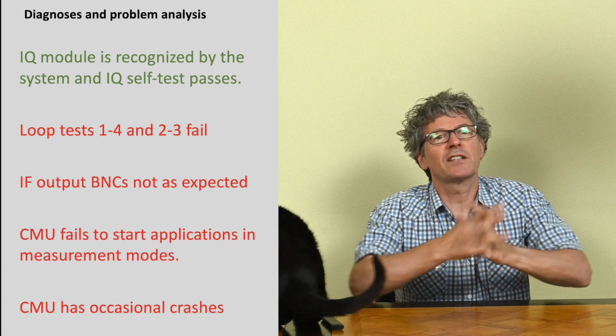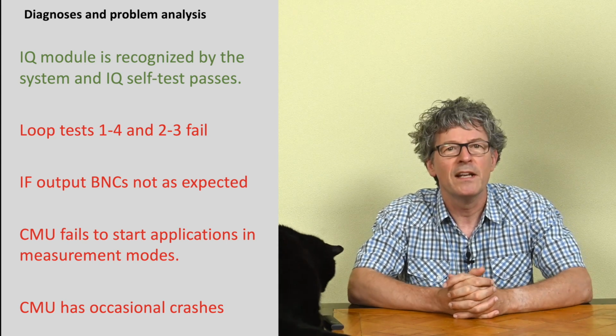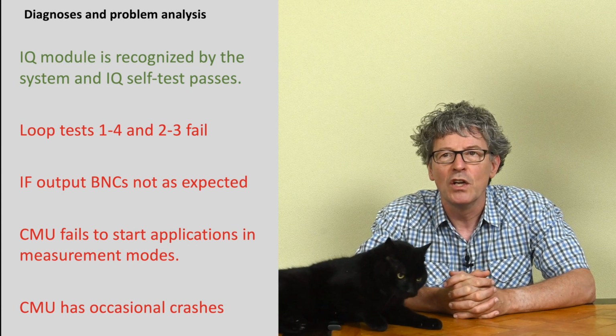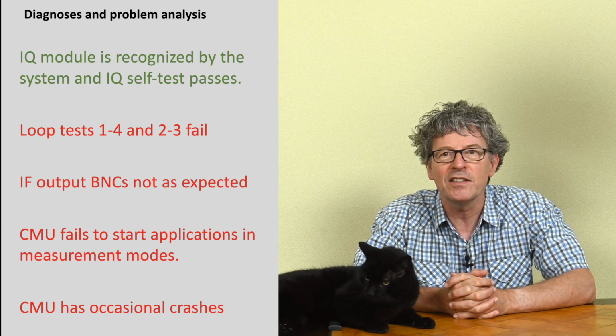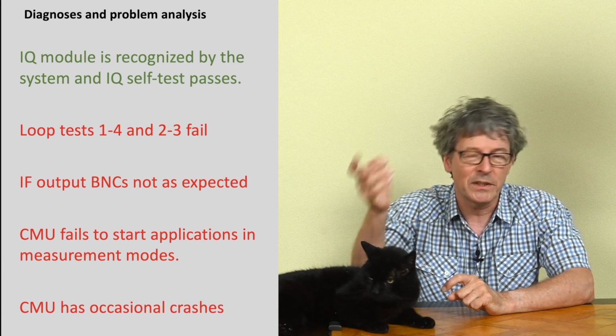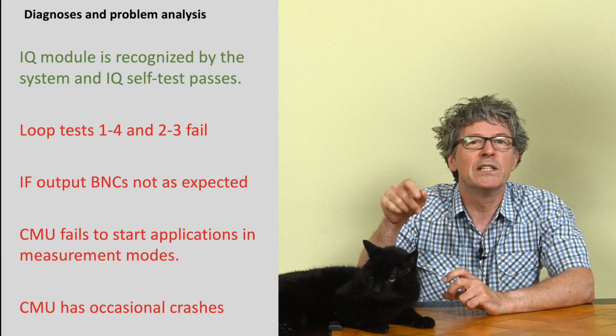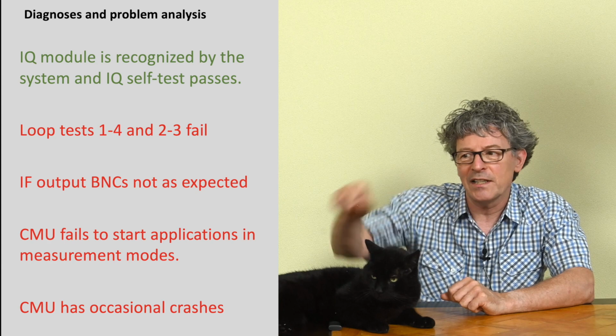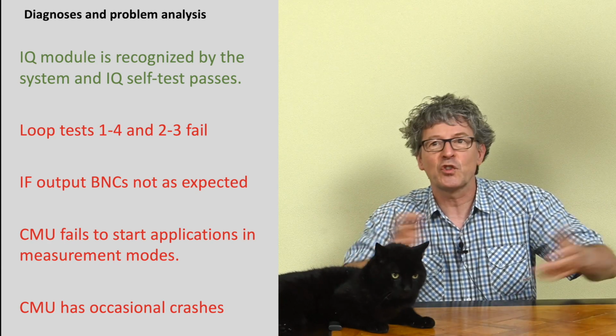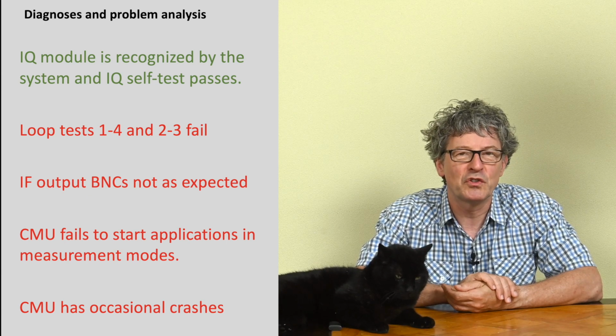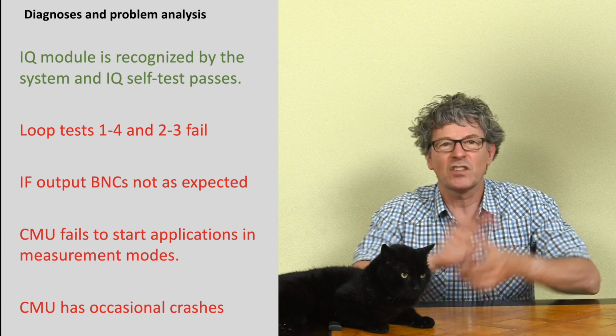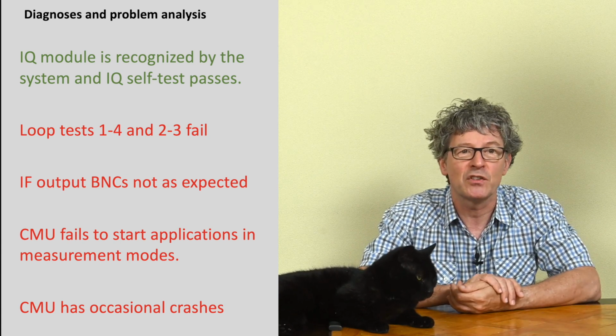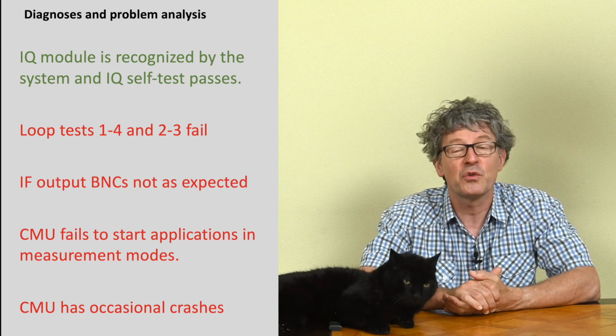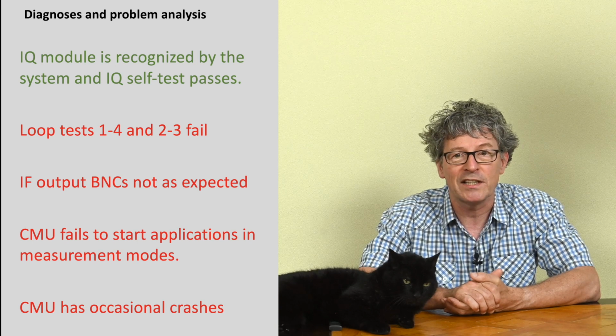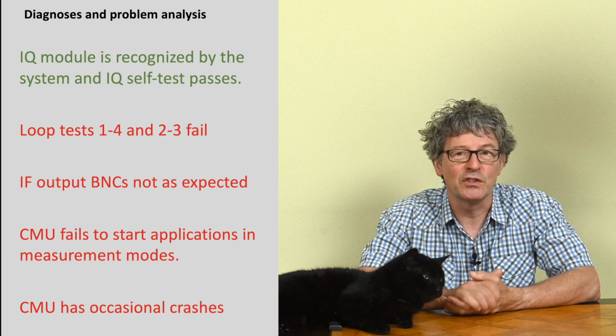Much more disturbing, and something that got me stressed, is that the CMU starts to behave in an unpredictable way. It fails to start applications in measurement mode. What is happening is, if I go to an application, normally it's already running when you go to it, but it's stopped or halted, and when I try to switch it on, I just see the generator light at the RF port going on and off for a second, and it stops again. That doesn't look good to me at all. I've never seen it behaving in such a way before. Something is wrong. It's not able to start up the application. And even worse, the CMU starts to have crashes. When I'm in measurement mode, it crashed a couple of times, even trying to boot itself. Yeah, so it really doesn't look good.